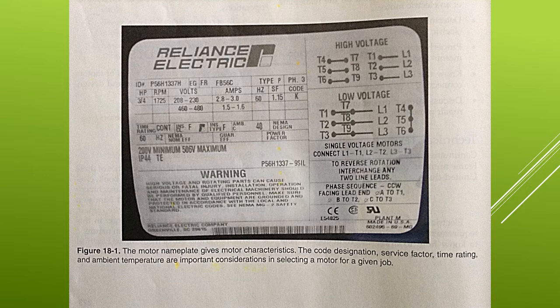time rating, RPM rating, design letter, frequency in hertz, number of phases, insulation class, load rating in amperes, locked rotor code letter, voltage, duty, ambient temperature, and service factor. Other information such as serial number, model number, bearing numbers, and efficiency ratings is often also included.